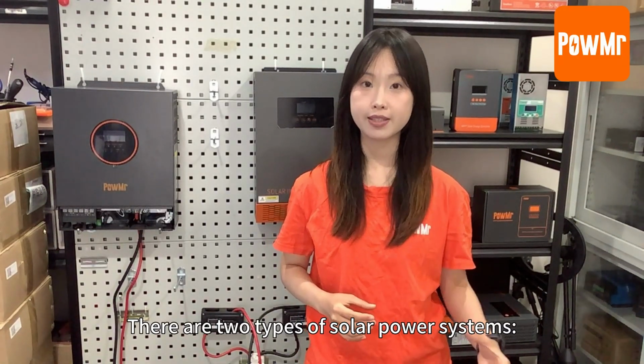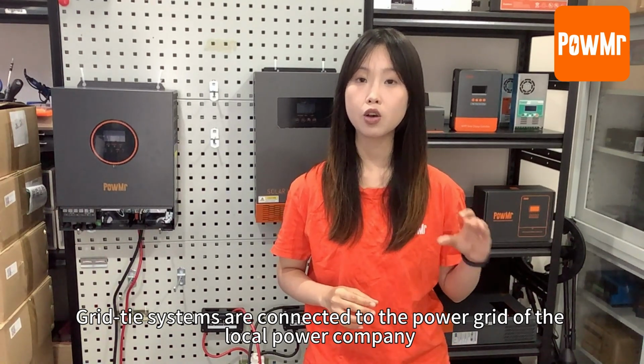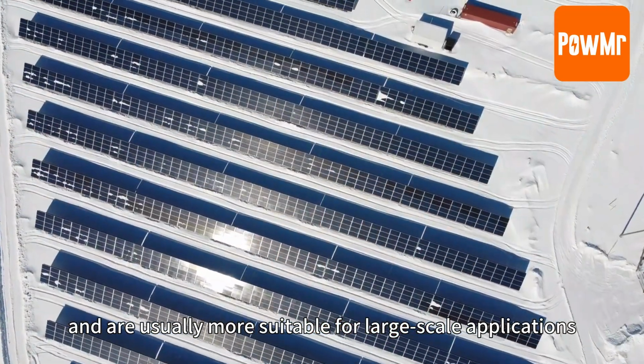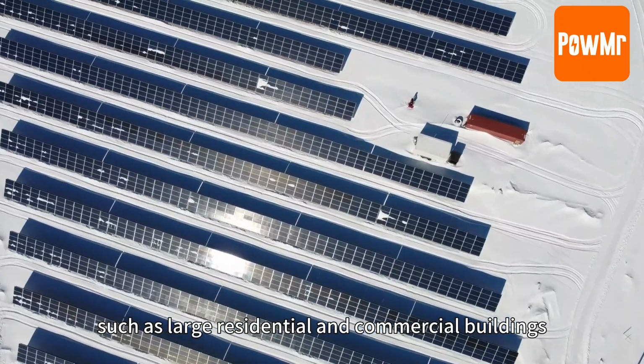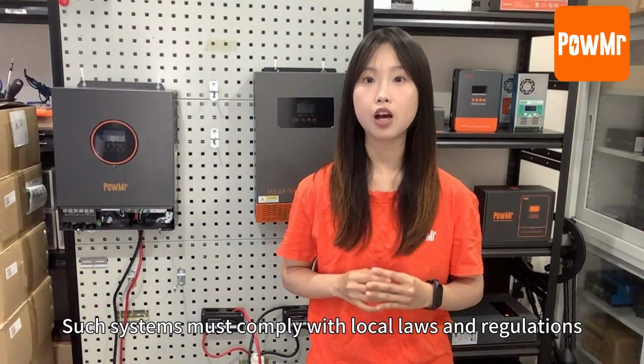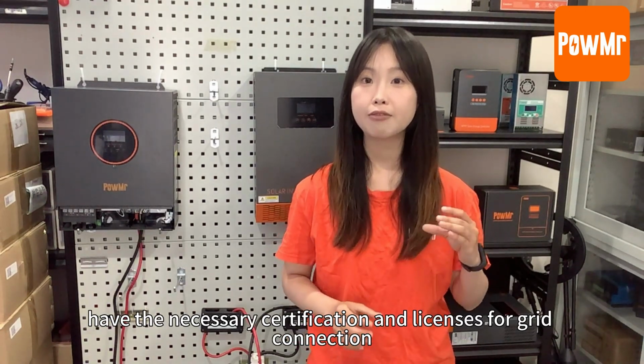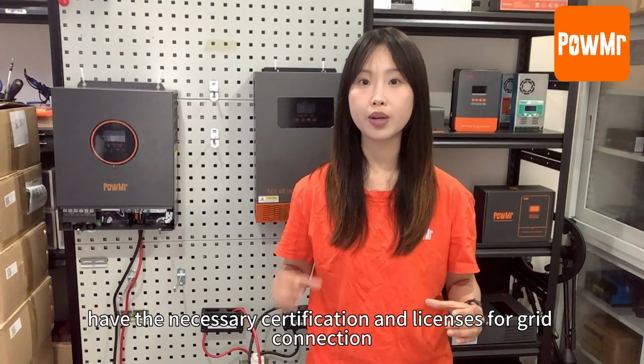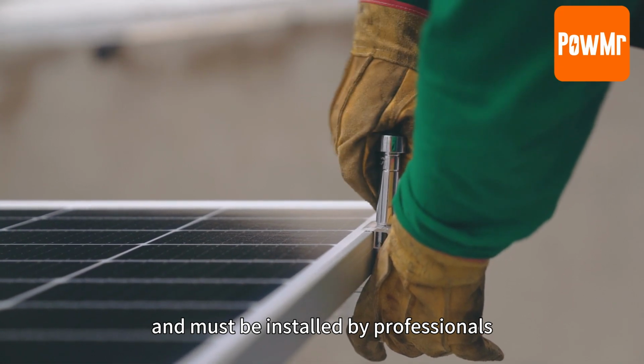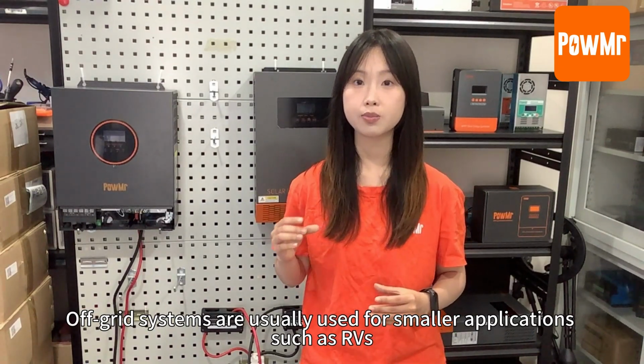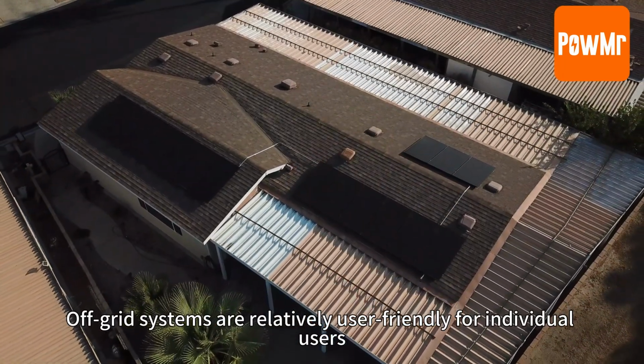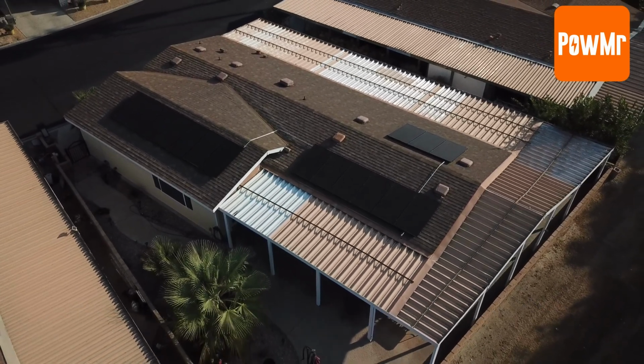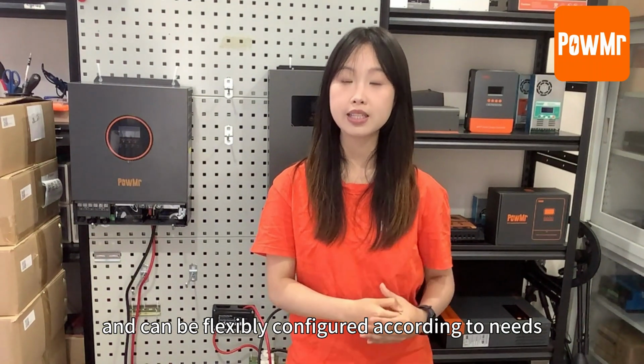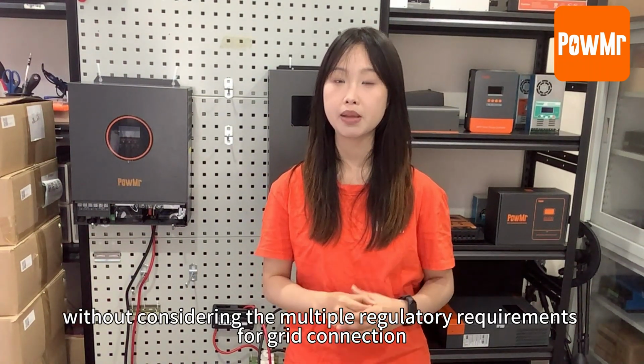There are two types of solar power systems, grid-tied systems and off-grid systems. Grid-tied systems are connected to the power grid of the local power company and are usually more suitable for large-scale applications, such as large residential and commercial buildings. Such systems must comply with local laws and regulations, have the necessary certification and license for grid connection, and must be installed by professionals. Off-grid systems are usually used for smaller applications, such as RVs, trucks, boats, and homes. Off-grid systems are relatively user-friendly for individual users and can be flexibly configured according to need without considering the multiple regulatory requirements for grid connection.